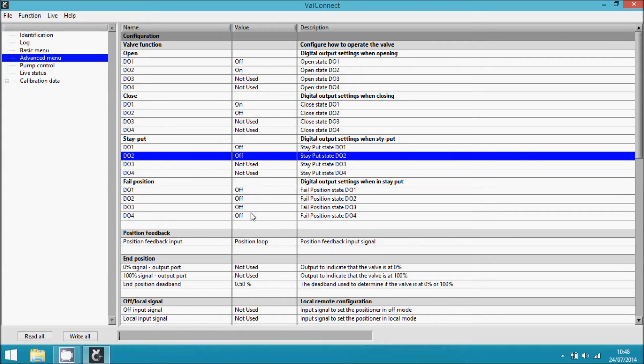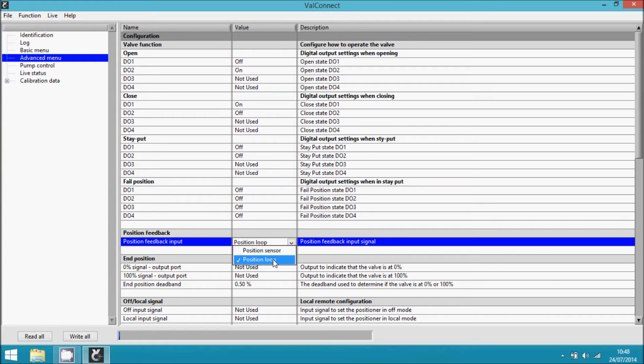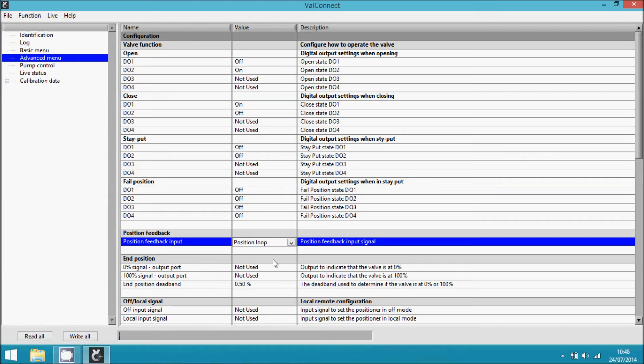The next step is to configure the position feedback, which can be chosen here. You can choose from position sensor or position loop depending on whether you have a potentiometer connected or a 4 to 20 mA signal. We have a 4 to 20 mA signal, so we press position loop.